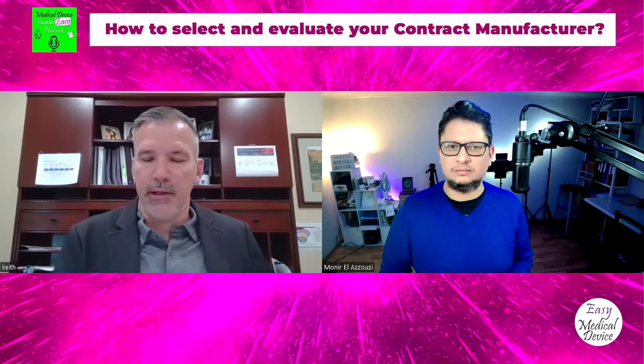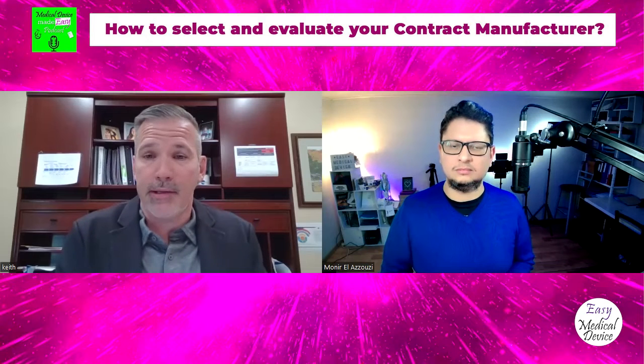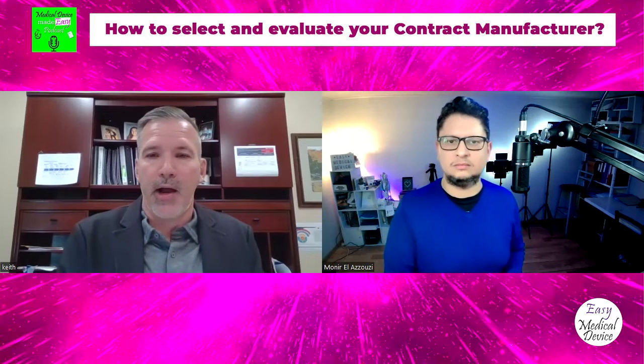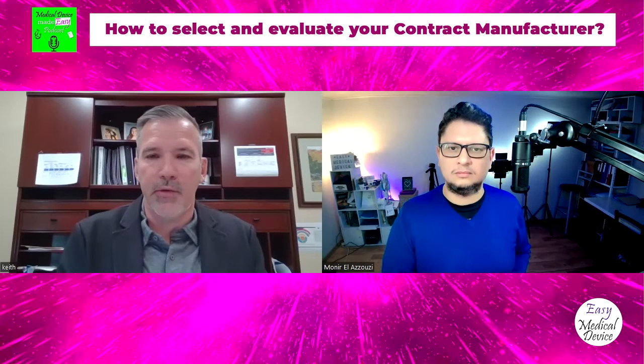Yeah, certainly. We want to avoid, right? To get costs down, you don't want to have 100% inspection. So the process that is most commonly used is validation. Can you validate that process and avoid designing a product that the process can't be validated? So early on in the design, start thinking about, do I have a contract manufacturer that I can validate this process? If not, right, I'm going to 100% inspection, especially on a class 2 device, and 100% inspection, if you have a decent volume, is going to be very costly. And so it really comes down to that design and the process working together to do the validation.